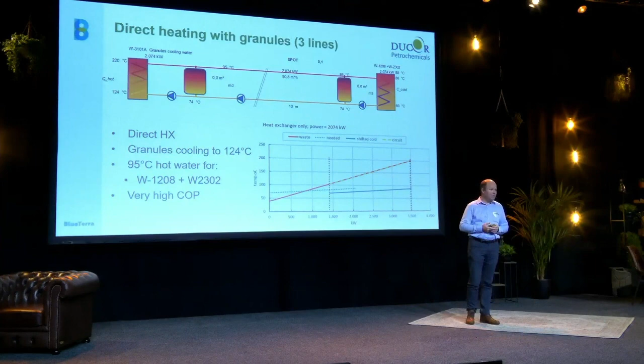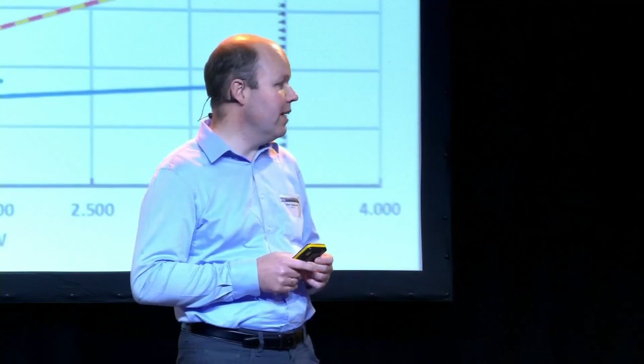So before we dive into a heat pump, as a consultant, you always think, do we really need a heat pump for this? Or is there probably another solution? If we check the level of the heat that's available in the granules, that's around 220 degrees centigrade. Of course, those granules need to be cooled rather quickly to the lower temperatures, and nowadays cooling water is used for that: 60 degrees cooling water, or 45 degrees, which heats up to 60 degrees. But if we try to make use of this very high level heat by using a heat stream of around 75 degrees and heat that to 95 degrees, we already have heat available at the level that we need it.